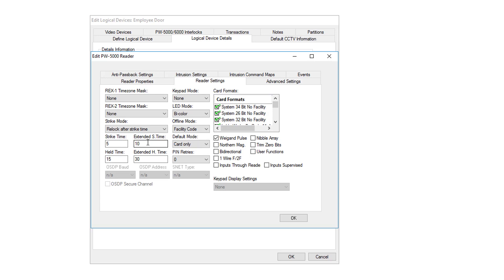To the right of this, you'll see your extended strike time and extended held time. These are set up to honor an ADA setting in Americans with Disabilities Act that may be assigned to a card. If the setting is found, it will use these extended times to give the person more time to get through the door and to allow the door to close.